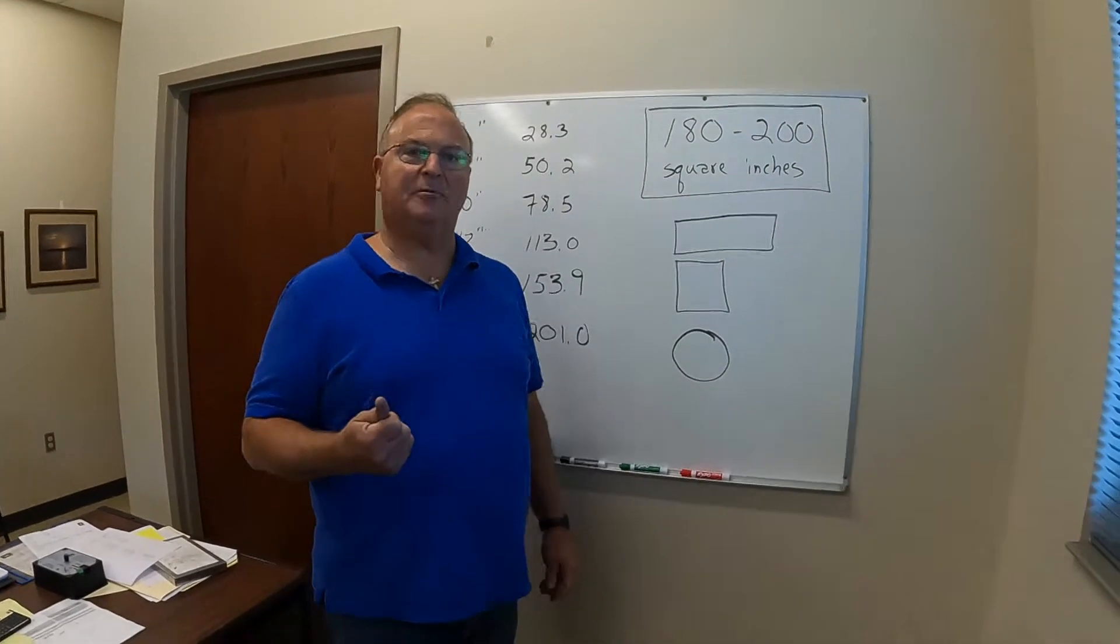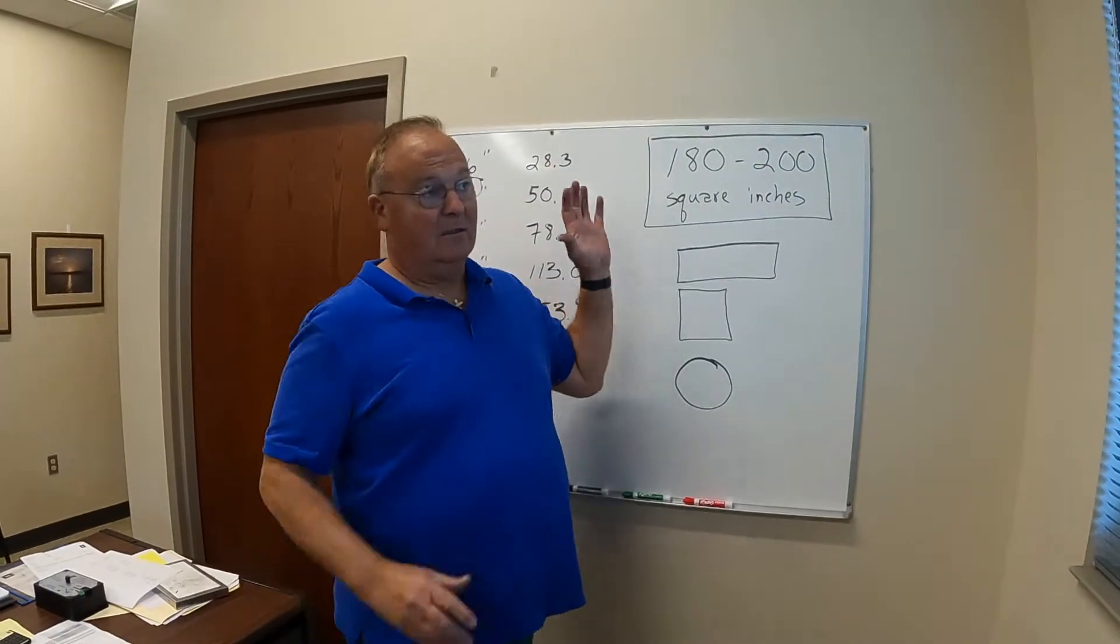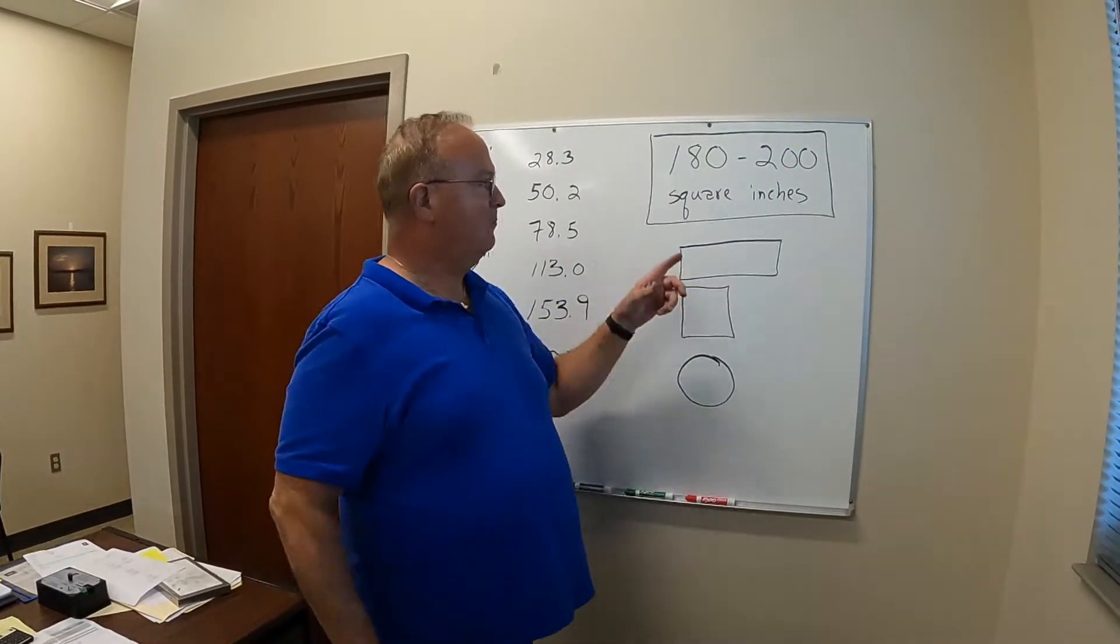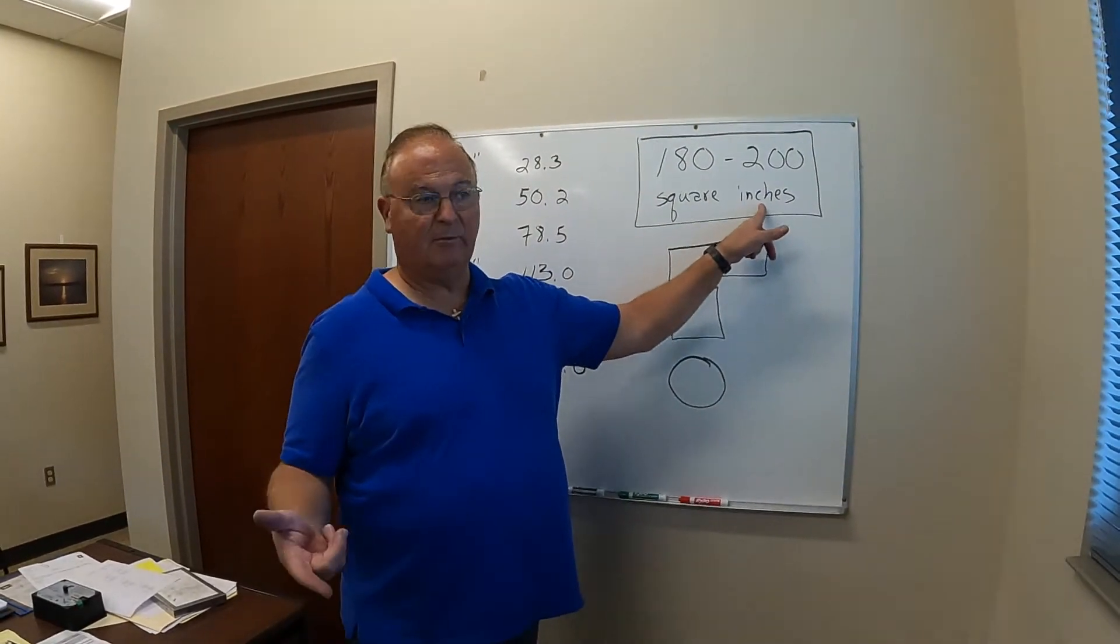So when you're hooking your plenum up to your ducting, as I mentioned, the ducting coming off the plenum, we want between 180 and 200 square inches, so length times width.